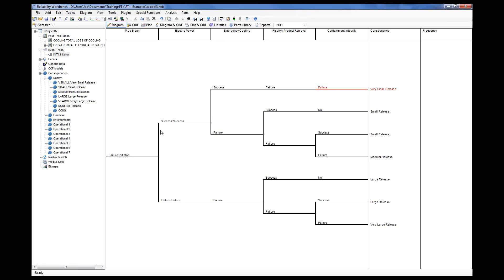For the very small release, you'd put events under NOT gates since the success branch is not a failure. That's one of the ways fault trees and event trees overlap — they use the same calculation methods. Technically, anything modeled in an event tree could be modeled with multiple fault trees, one for each consequence, but the event tree is easier to read and a more logical layout for evaluating consequences. Event trees are naturally suited to that sort of thing.